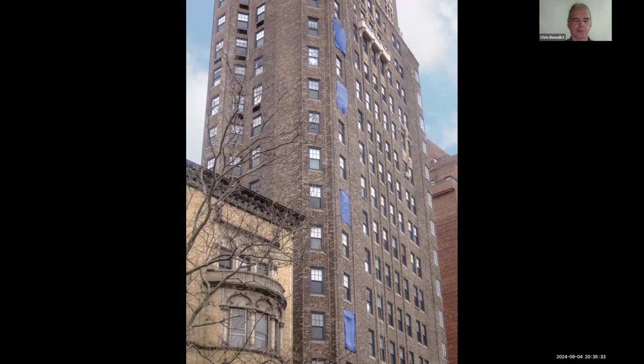And here's a taller building. They're changing windows today, the day I took this photo. And you see up at the top, the blue tarps are puffed out. And in the middle, not much happening. And in the middle, if you want to sound fancy, you call it the neutral pressure plane. And at the bottom, the stack effect is pulling the tarp in. This is, of course, winter. You can tell from no leaves on the tree, and you can tell from the stack effect moving the air upwards within the building.